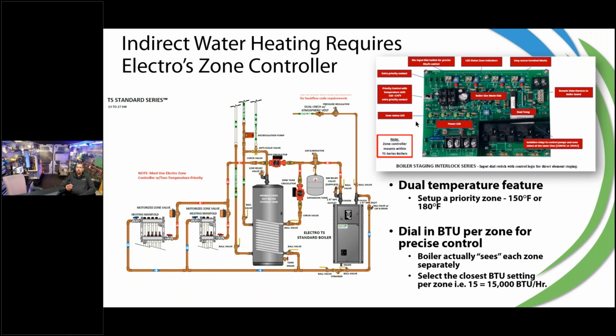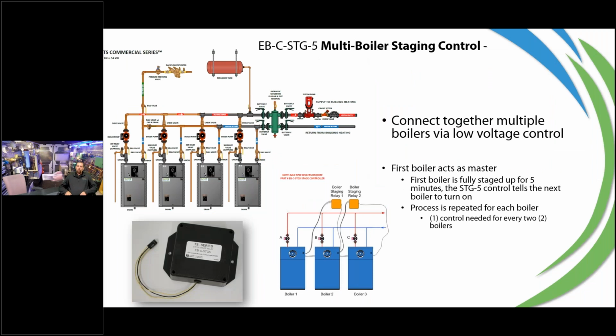We also have the addition of what we call a boiler staging control. Sometimes when we get into these larger homes, instead of selecting one larger boiler, it might be better to go with some smaller boilers that we put together. We can do 2 boilers to a control, and up to 5 stages. Five little boilers there would be pretty wild - I'd like to see that.